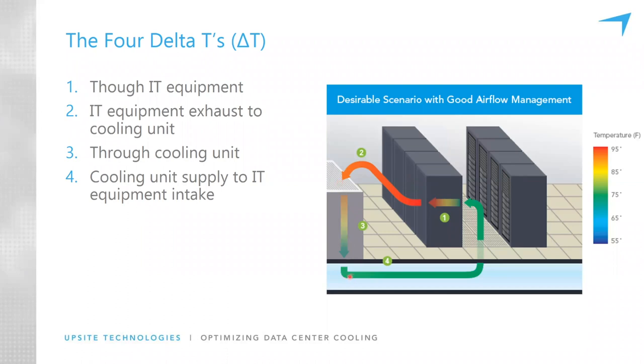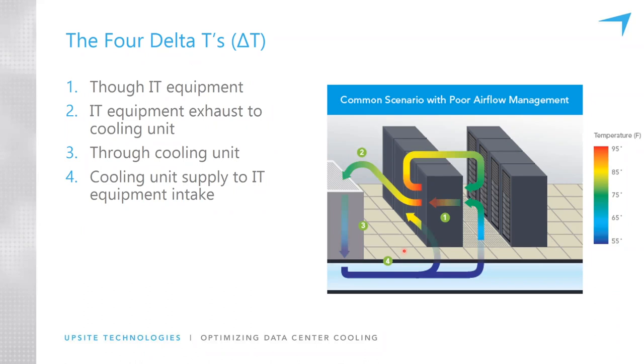Now, you wouldn't think that these would change very much, delta T4 and delta T2. And in this example, they're drawn at the same temperature. The air comes out at 75 degrees and the warmest intake temperature to IT equipment is maybe 80 degrees, and that's ideal. The air comes out at 95 or 100 degrees, and it returns to the cooling units at around 90, 95 degrees. That is the way we would like to have our facilities. However, this is the way they actually are.